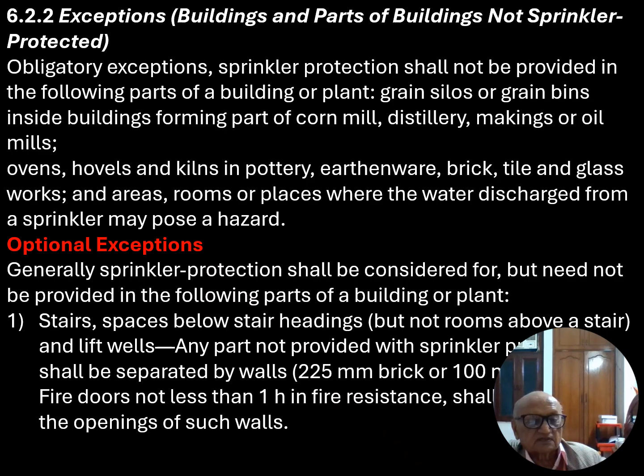Generally, sprinkler protection need not be provided in the following parts of a building or plant: stair spaces below stair headings, but not rooms above a stair. These are the below portions. Normally, people provide electrical switchboards there. And in lift wells, any part not provided with a sprinkler shall be separated by walls of 225 mm brick or 100 mm concrete. Fire doors shall not be less than 1 hour in fire resistance.